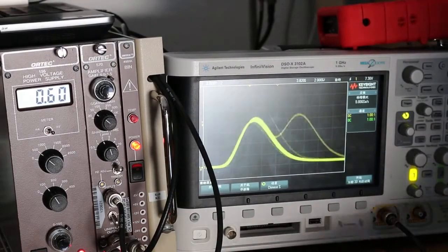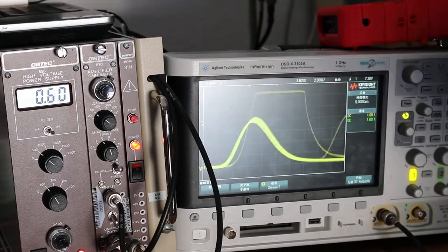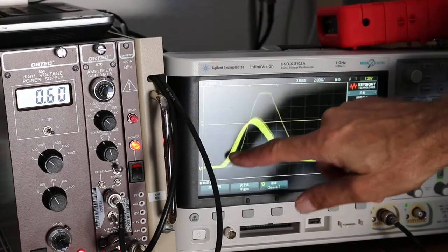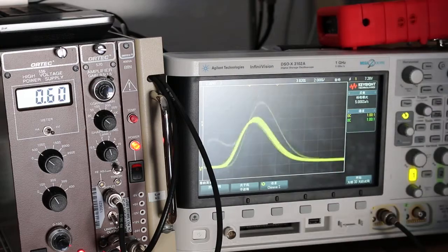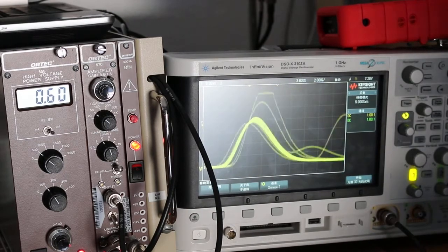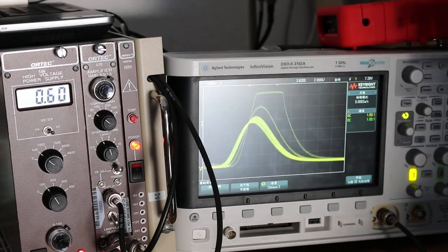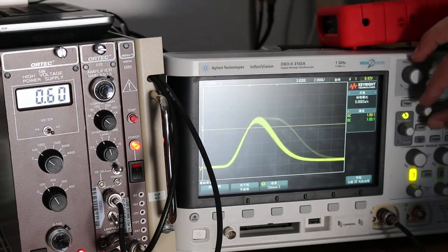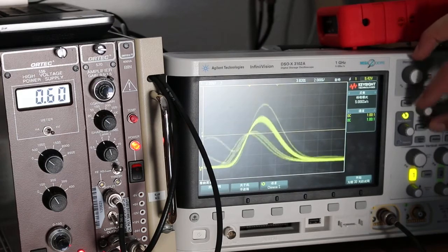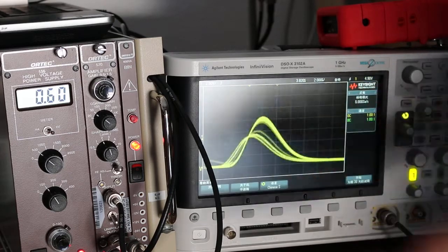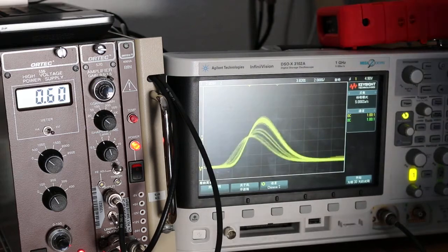Okay, so we're trying to work on what this scintillation signal means, and I've artificially set the trigger source of this oscilloscope so high that I'm only seeing the energy for the highest energy gamma rays that are coming out of the detector, and for the cesium-137, 662 keV. So what happens then is I lower the trigger level a little bit, then I'm allowing lower energy pulses to be seen by the oscilloscope. See, we're starting to get this region all filled in here with pulses of other amplitudes.